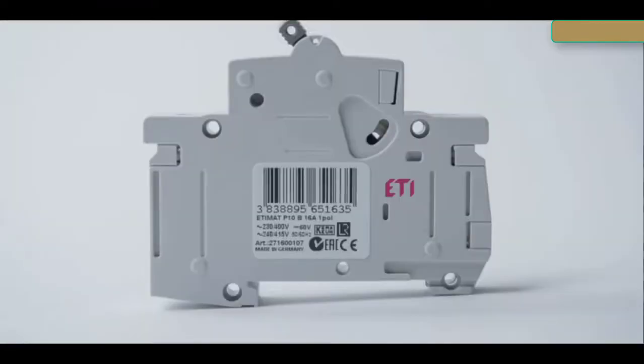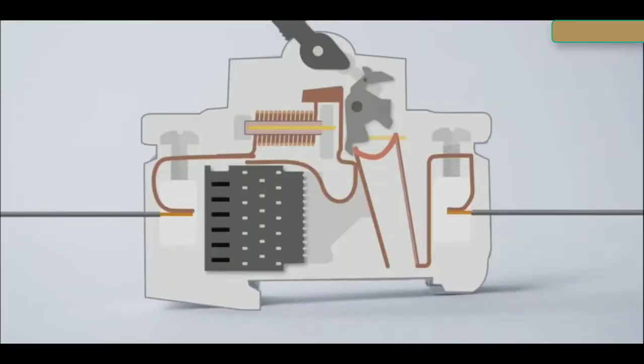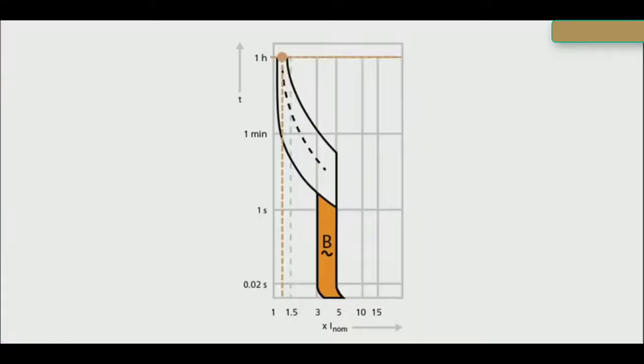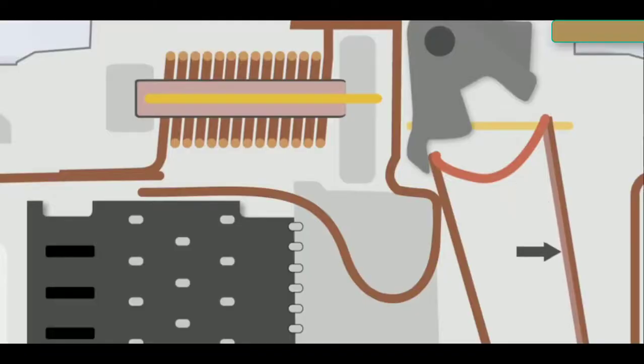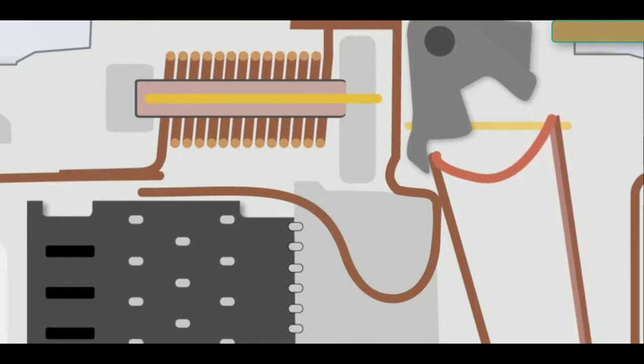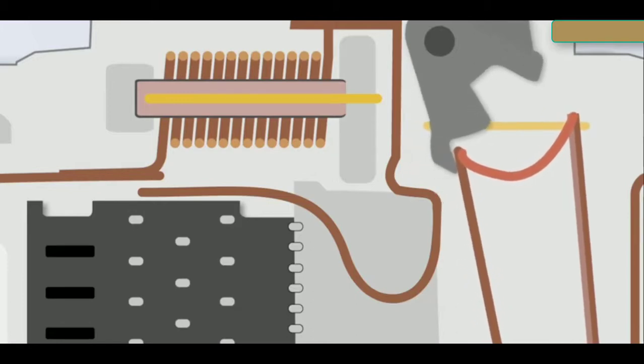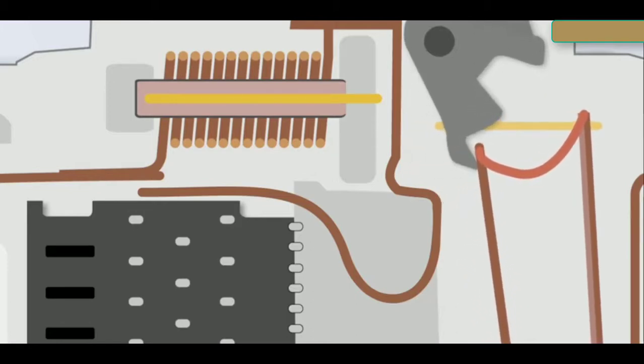Inside of an MCB, the path the current is taking across the closed contacts is visible, as are the tripping components. The higher the amplitude of the overcurrent, the faster an MCB must trip. This is achieved with a metallic element consisting of two different metals, which are heated up by the current flow. The two metals expand at different rates while they're heating up. An overcurrent that is present long enough will eventually activate the bimetallic element.